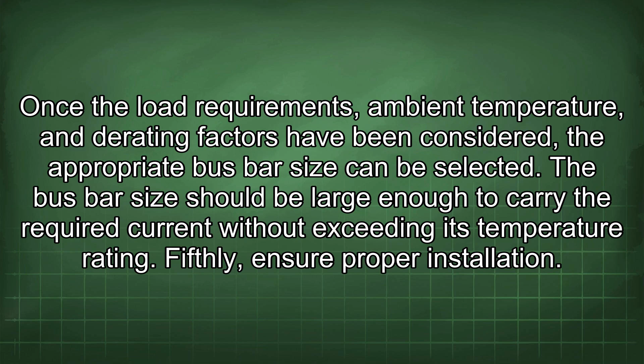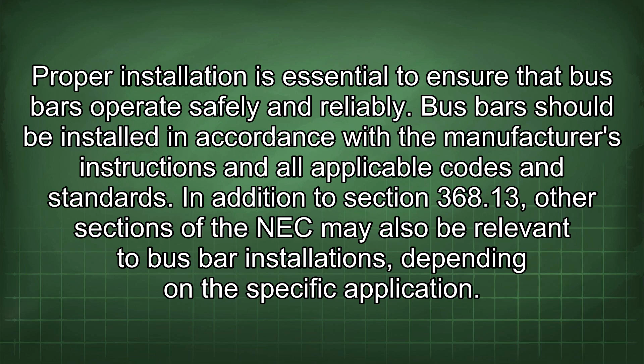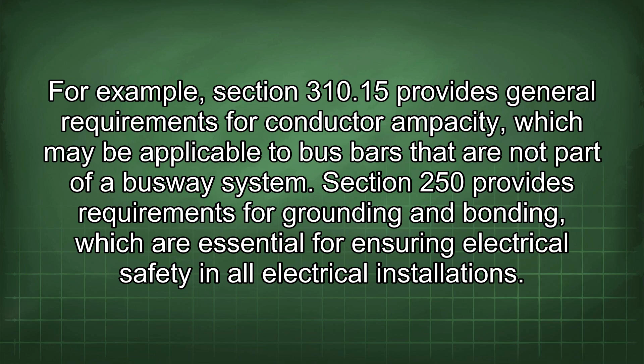In addition to Section 368.13, other sections of the NEC may also be relevant to busbar installations depending on the specific application. For example, Section 310.15 provides general requirements for conductor ampacity, which may be applicable to busbars that are not part of a busway system. Section 250 provides requirements for grounding and bonding, which are essential for ensuring electrical safety in all electrical installations. Section 408 covers switchboards and panelboards, which often incorporate busbars as part of their internal construction.